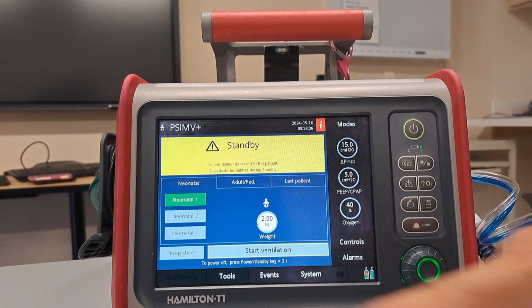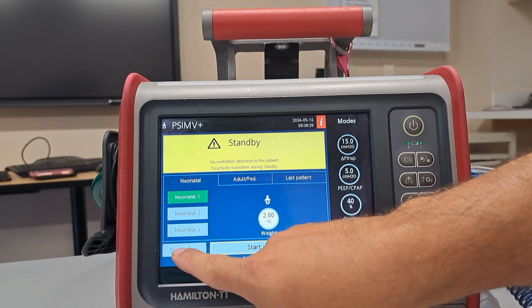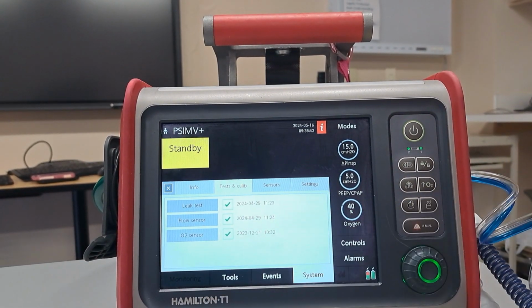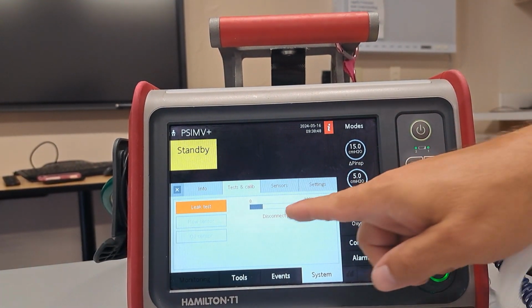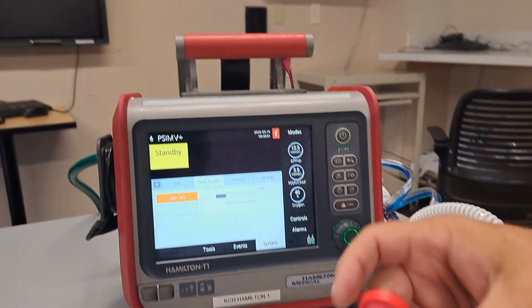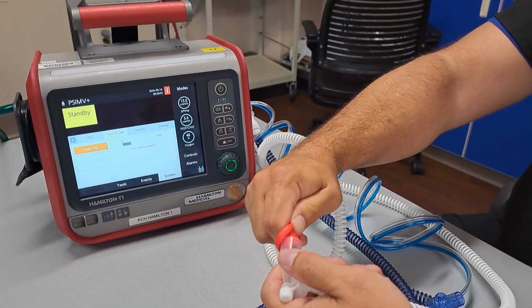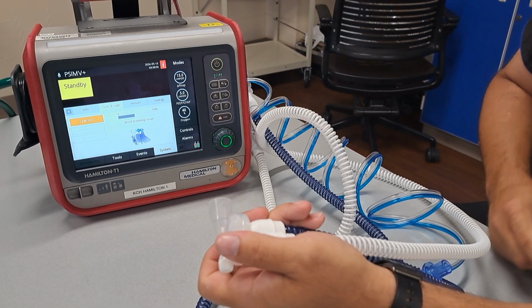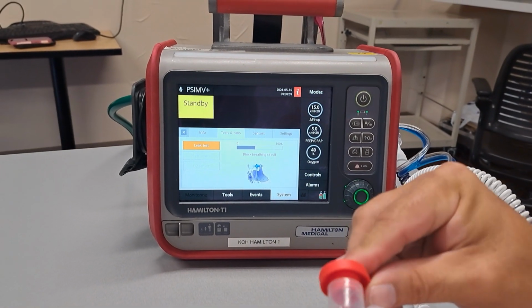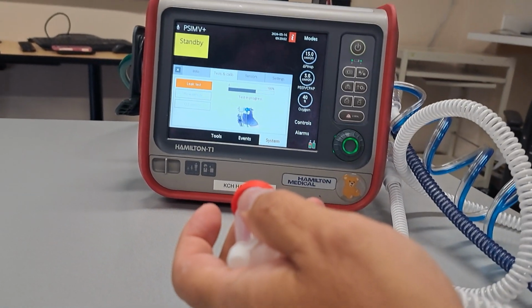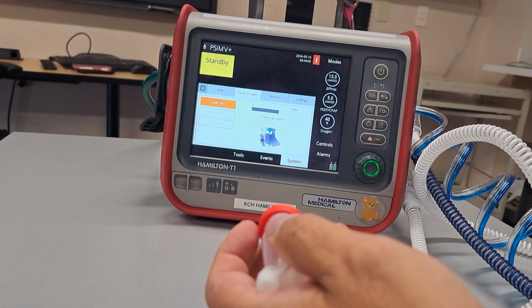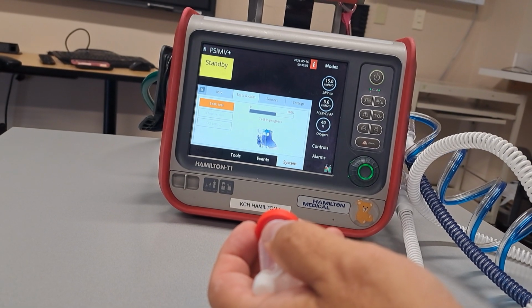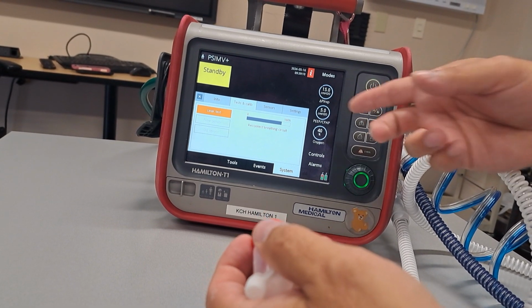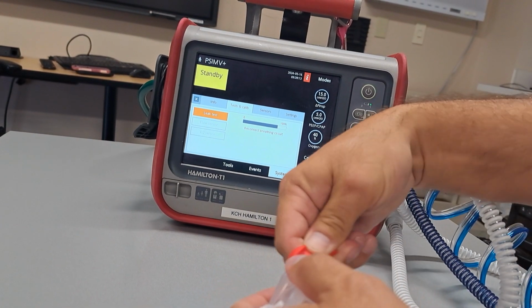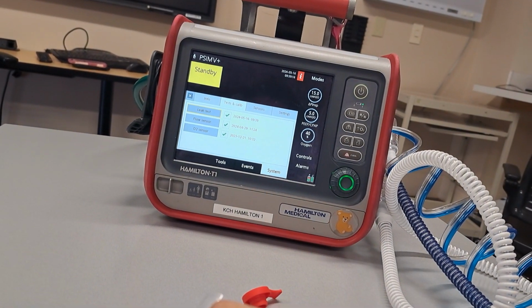and now we will do the pre-op test, which is this button right here. Select it. And first we'll do a leak test. Tells you what to do right here. Disconnect the patient. So I'm going to take the red stopper out of the end. Now it says to block the breathing tube, so I'm going to connect this back. Reconnect the circuit, so I'm going to take this off, and the leak test is done.